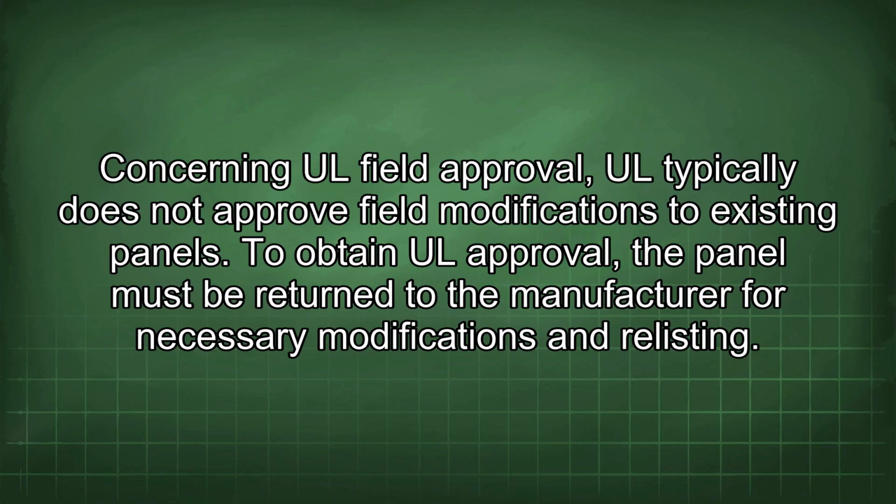Concerning UL field approval, UL typically does not approve field modifications to existing panels. To obtain UL approval, the panel must be returned to the manufacturer for necessary modifications and relisting.